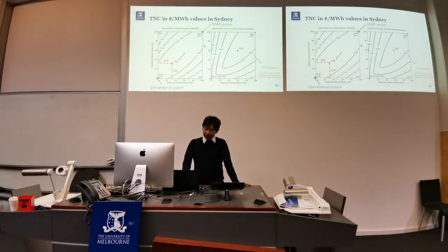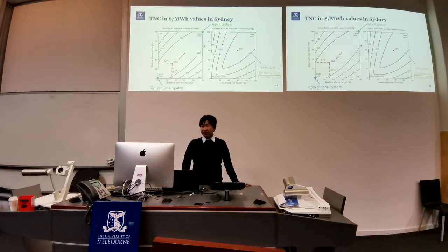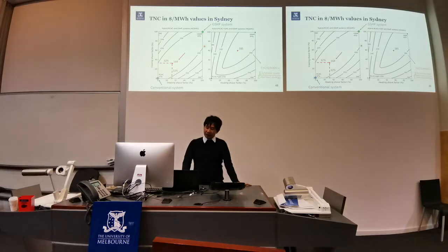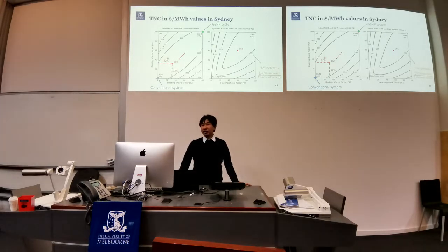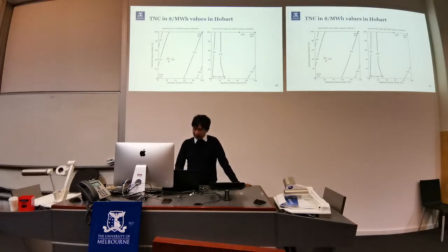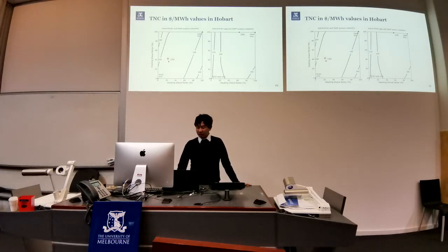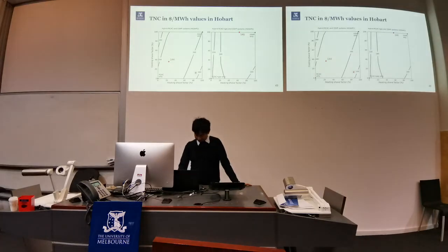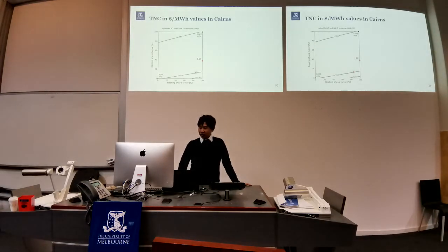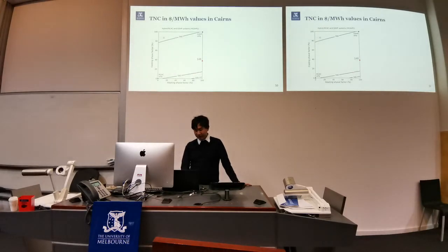One more thing: in a location with a balanced climatic condition, such as Sydney, both the heating and cooling shear factors play some part in the normalized cost, as you can see by the circular shape of the contour line. In a heating dominant climate, such as Hobart, only the heating share factor has some effect. As you can see, the contour line is more in the vertical orientation. In a cooling dominant climate, such as Cairns, again only the cooling share factor has some effect, where the contour line is in a horizontal configuration.